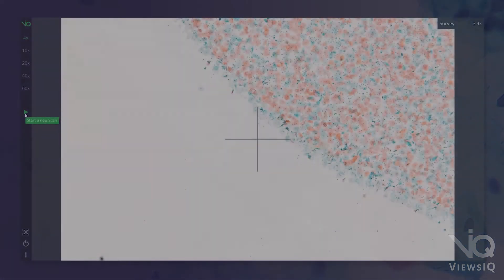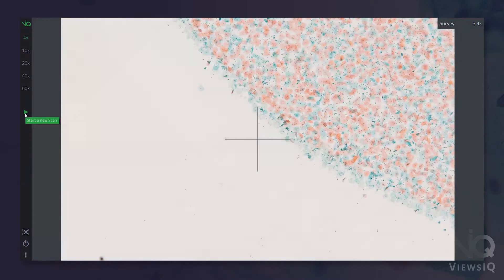When you launch Panoptic, you are presented with what the microscope is seeing. To start recording, simply hit the Start Scanning button or the spacebar.